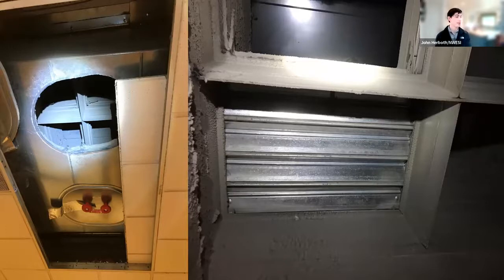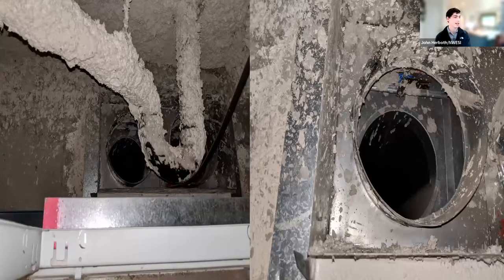Sometimes access is really great. You can fit your whole body in this type of space. And then sometimes access is terrible and it's been spray coated. Any fusible link that you can visually check for cracking or damage, you can put it back in as long as you can inspect it. If it's coated with anything, you now have to take it out and put a new one in. Somebody asked what the reasoning for that is, and we'll get to that. We'll table that one for the Q&A.